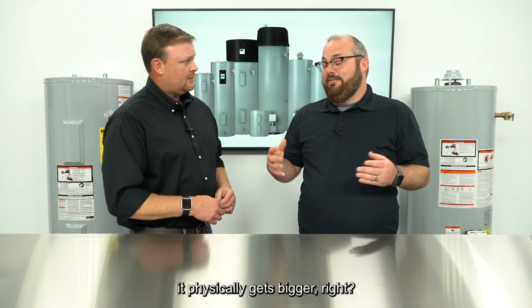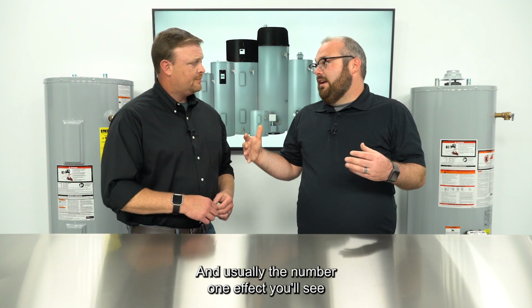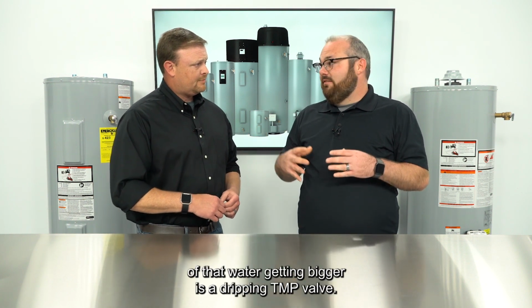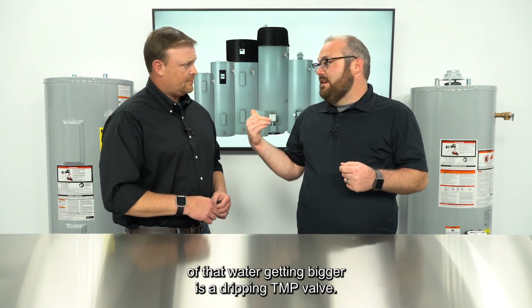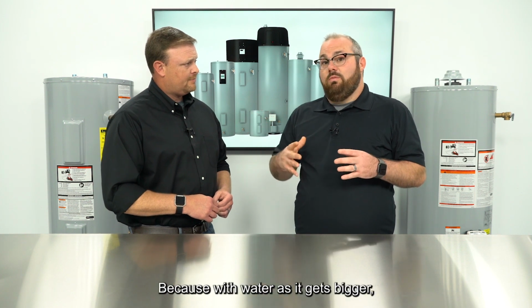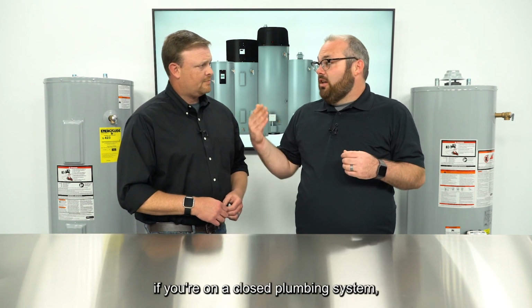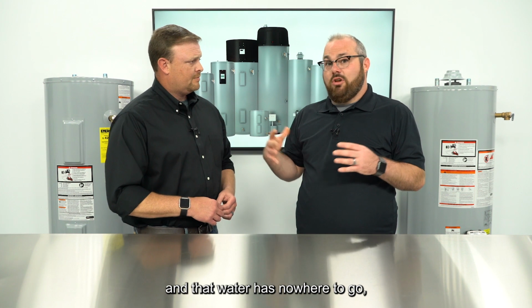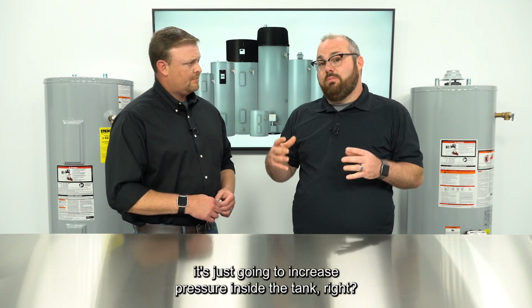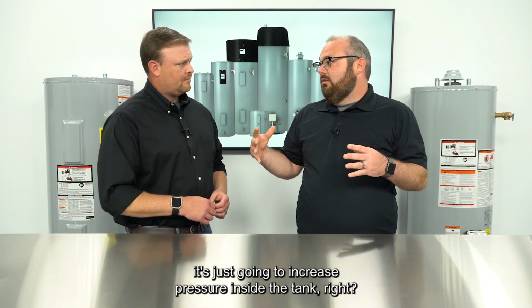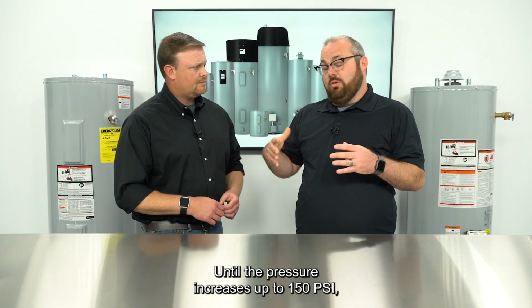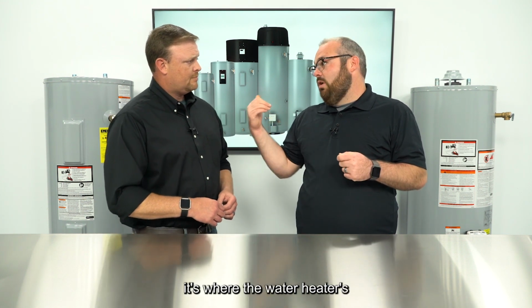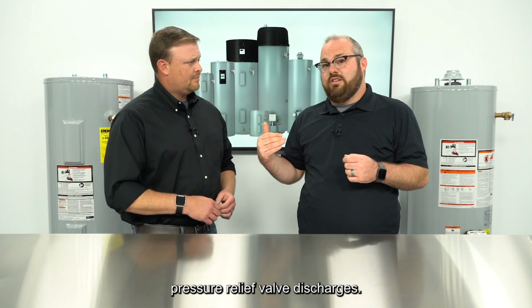Well, when we heat water, it physically gets bigger, right? And usually the number one effect you'll see of that water getting bigger is a dripping T&P valve. Because with water, as it gets bigger, if you're in a closed plumbing system and that water has nowhere to go, it's just going to increase pressure inside the tank, right? Until the pressure increases up to 150 psi, it's where the water heater's pressure relief valve discharges.